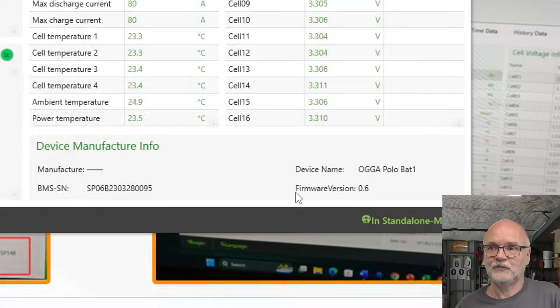To do the online update, we stop the communication, go to online upgrade, start the software, and connect via the virtual COM5 again, leaving all the other options as they are. Click on open, nothing happens. Click on browse for the firmware -- which one do we go? Here, 18, and then I've got the 100 amp BMS going in here. I've got version 10, and this is the file I want. So we click on open, and then we click on download.